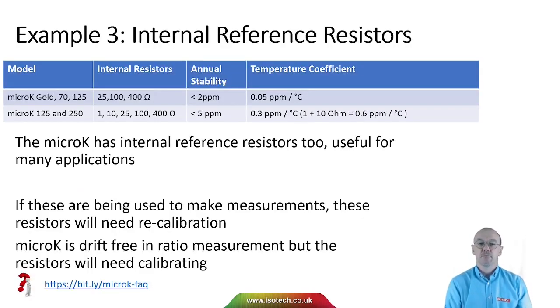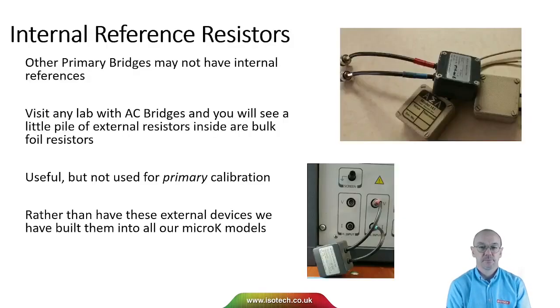And then the third example is using the internal reference resistors. The MicroK has a range of internal resistors. They're useful for many applications, but you wouldn't use those for primary metrology, like calibrating a fixed point cell or calibrating an SPRT to the lowest uncertainties. And if these are being used to make measurements, the resistors will need recalibration. So the MicroK's drift-free in ratio measurement, but the internal standards will need calibrating perhaps once a year. We've got more information about that on the FAQ link.